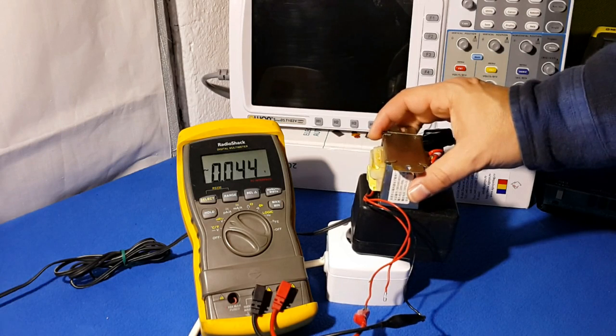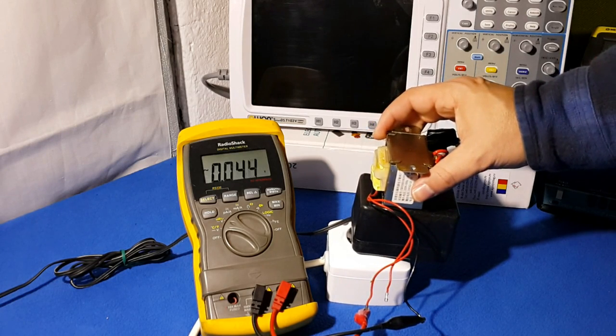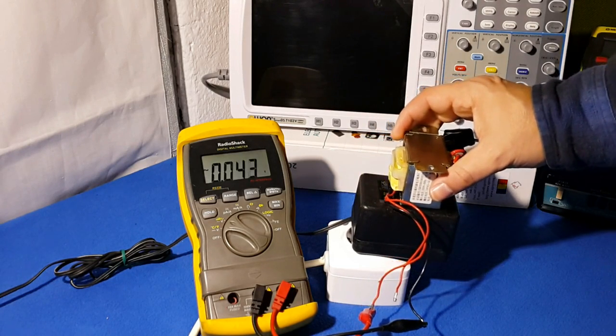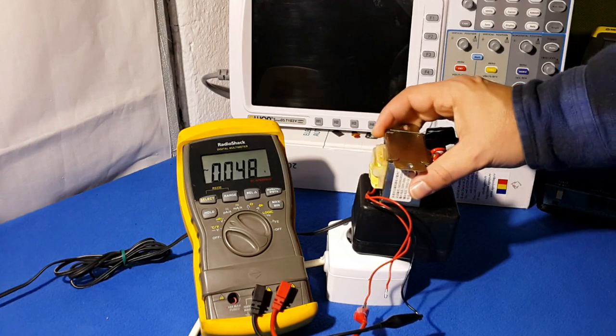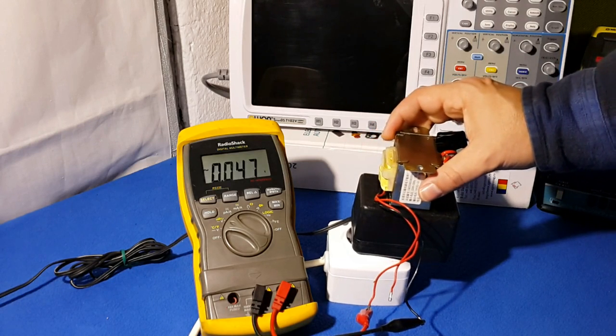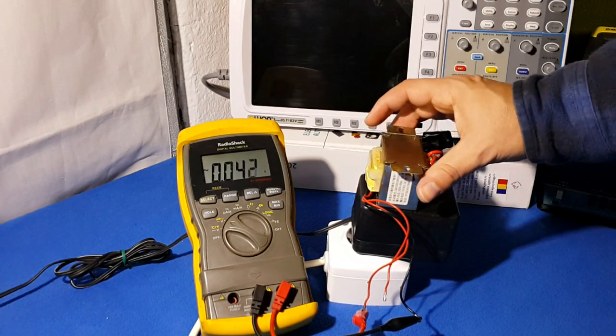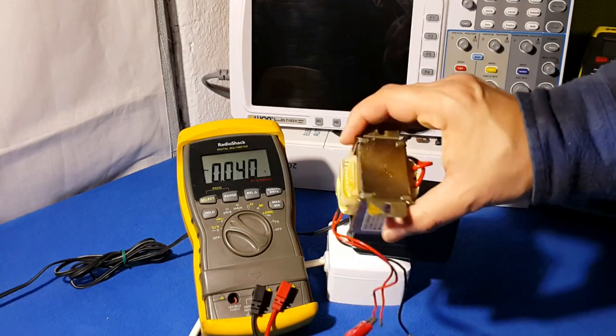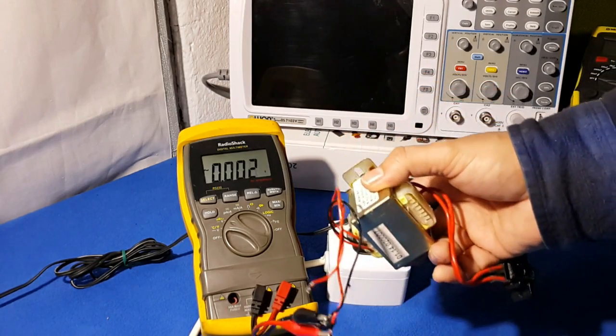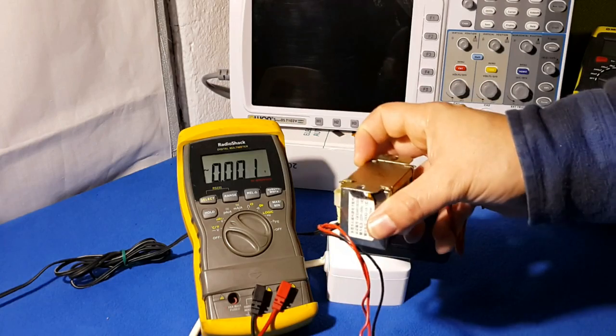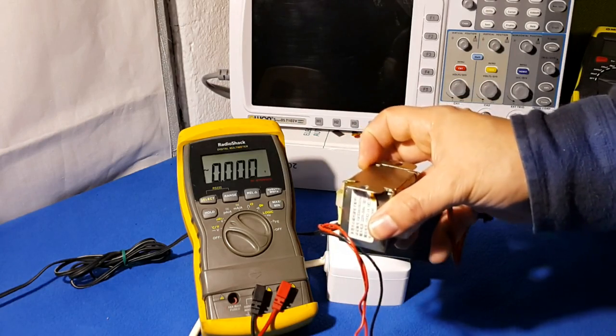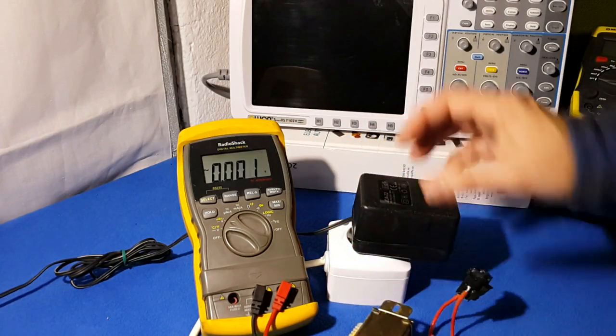About 40 millivolts is in the expectation with the ratio. So our transformer passed the induction test. Let's see now with the ohmmeter.